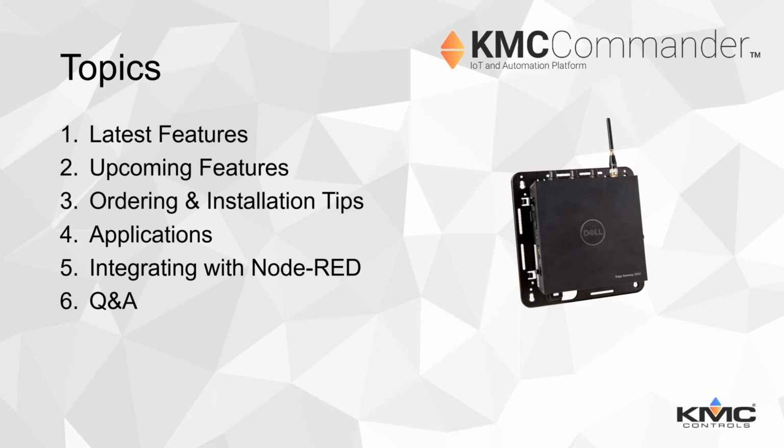What happens is Commander, the operating system, gets confused, and it assumes that if there's a gateway, there's cloud access, and it tries to use both ports, creating more problems. Yeah, and it'll slow down quite a bit. Yes. So don't use the same IP on port 1 that you use on port 2. Each interface has to be a different subnet, and you do not want to overlap subnets. So they have to be unique, completely independent subnets for all your interfaces.